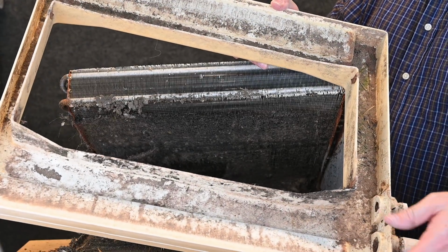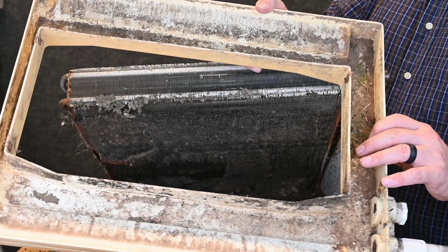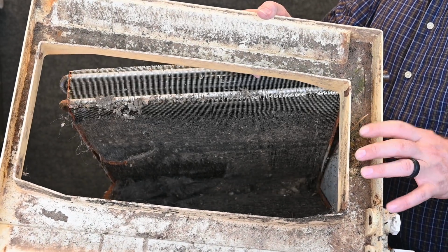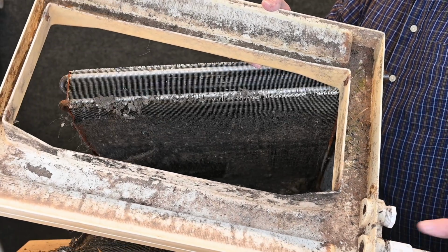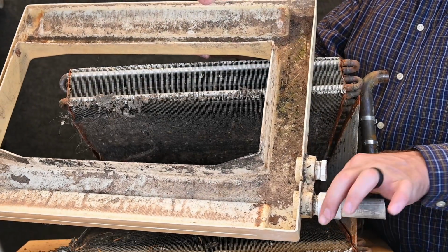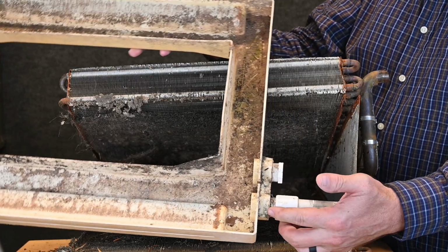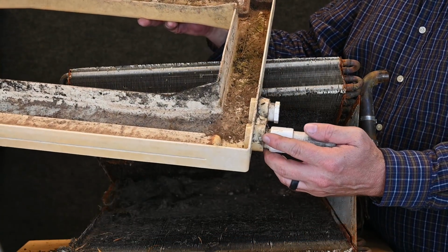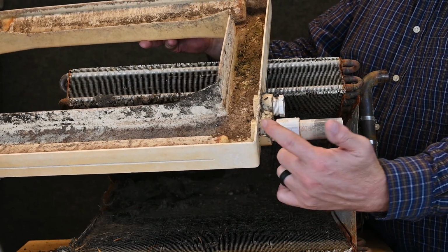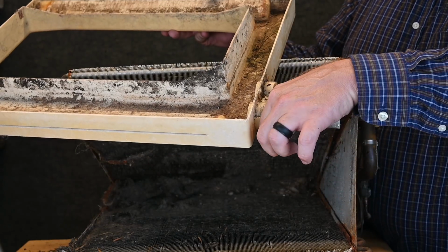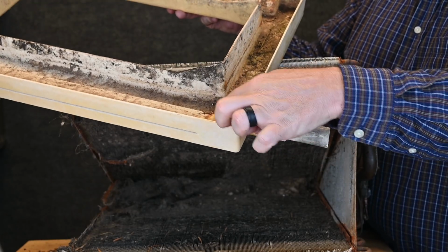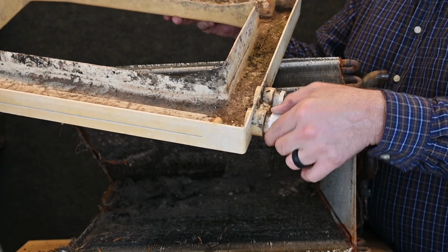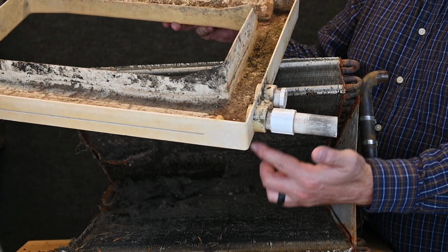Now this pan is made out of plastic. Most all the new ones are made out of some type of a composite plastic. The old ones are made out of metal that we just have to actually take apart and have rebuilt. Because it's plastic, when we screw our drain fittings in, this is called a field connection here. When we put this drain line in, we have to be careful that we don't crack this drain pan. One, if you push on it, too much pressure here, it will cause this pan to break. And also if you over tighten this connection, it can cause the pan to break, and then it's leaking water out.